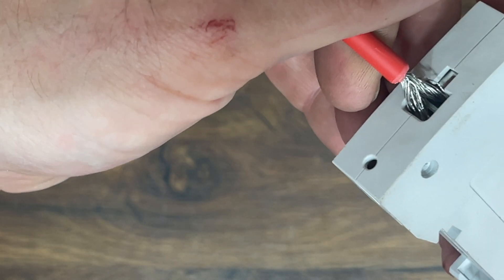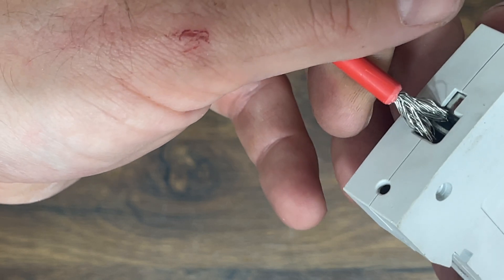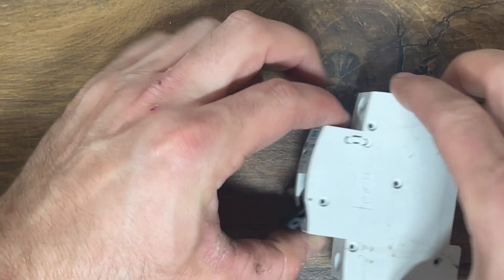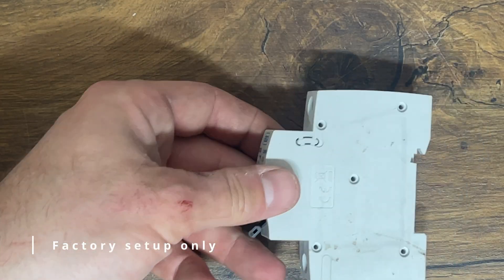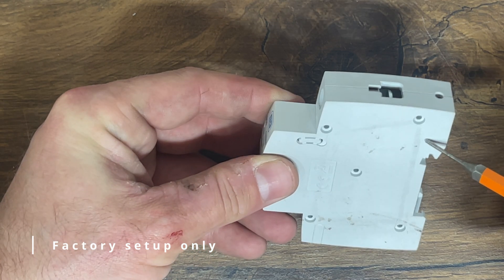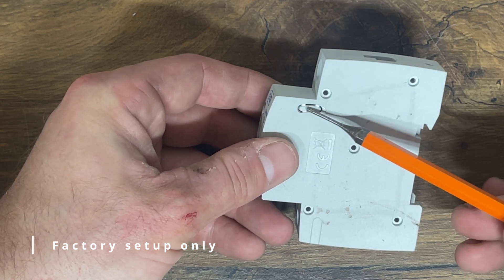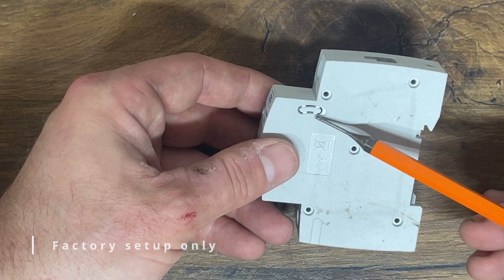Another issue is with stranded cables. You could end up in a position where some of the strands end up behind and some of them end up in front of the terminal, so you don't end up with a full, secure connection. Before we move on, we have a little screw terminal on the top for adjusting the bimetallic strip, which we will see a little bit later.